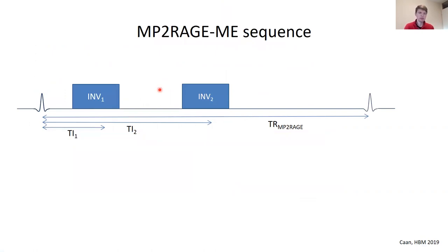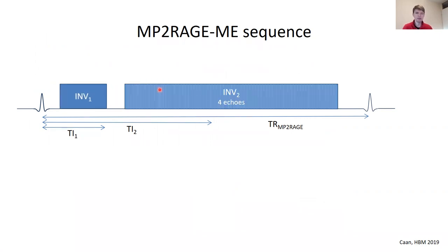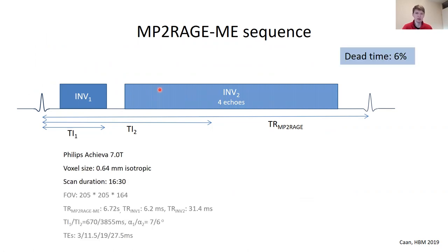Allow me to first go into the sequence, then into the motion robust imaging, before proceeding to accelerated imaging using deep learning. We started by building a multimodal sequence called MP2RAGE-ME — the multi-echo MP2RAGE sequence — by simply extending the second readout of the second inversion of the conventional MP2RAGE sequence to four echo readouts, reducing the dead time to six percent from initially more than 50 percent, giving us a flexible readout with a relatively long echo time for the second readout.